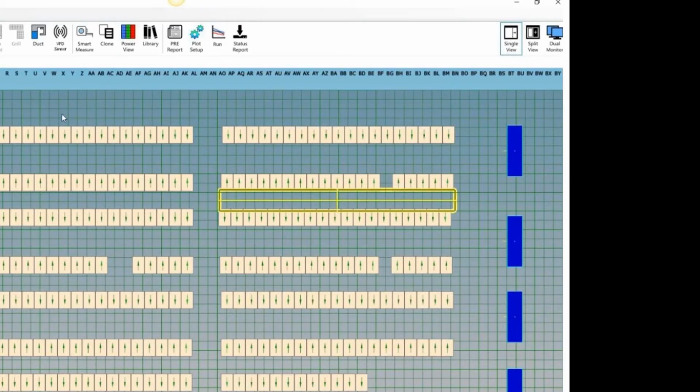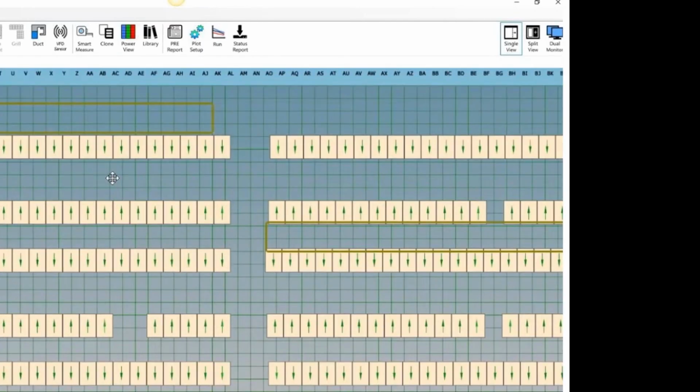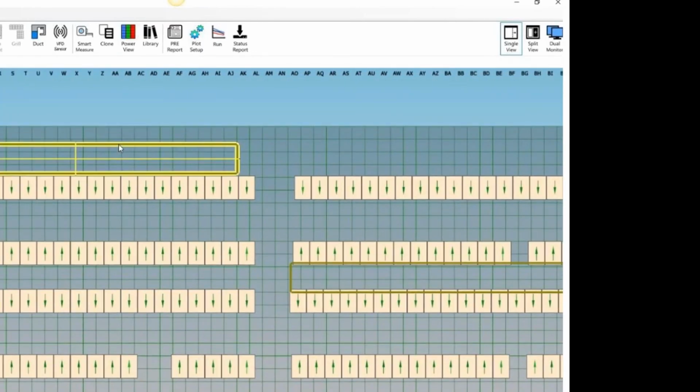They are set, I think, leaking at 5%. You notice they're slicing right through the racks. Those baffles go all the way to the floor. You can slice right through a rack in CoolSim and it won't bother it as long as you don't get in the way of the inlets.